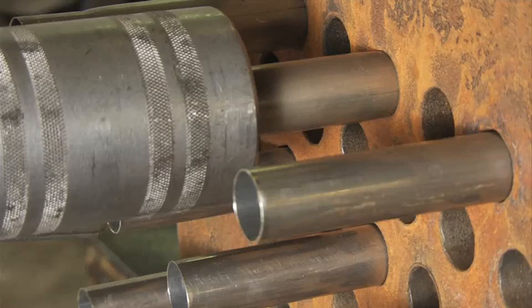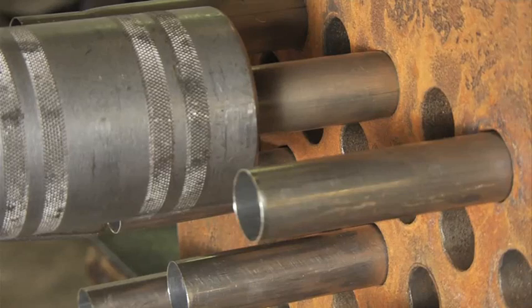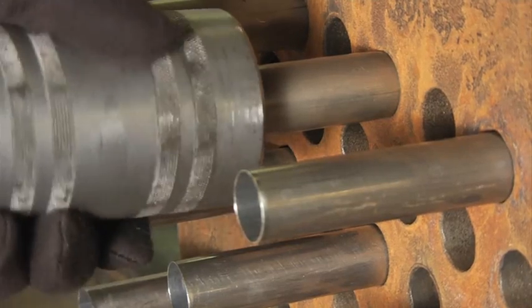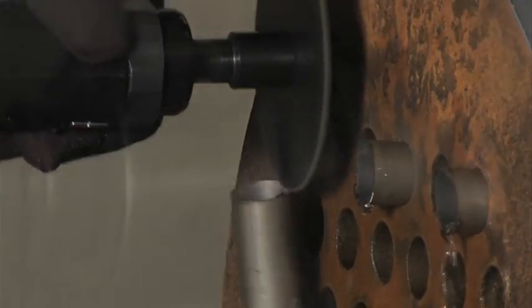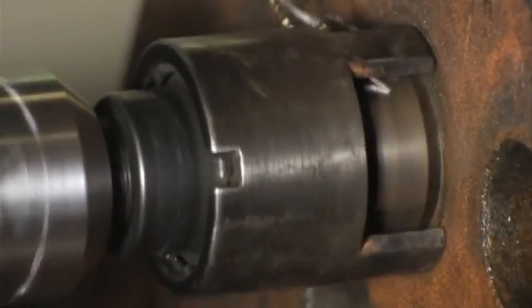When the expansion process is completed, the pressure is allowed to dwell and the chucks removed. Liner ends are cut and trimmed flush to the tube sheet, then roller expanded at each end, completing the repair.